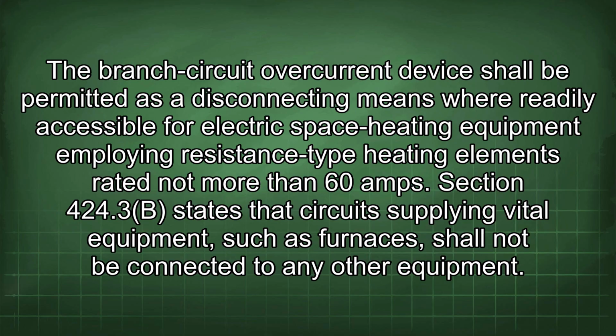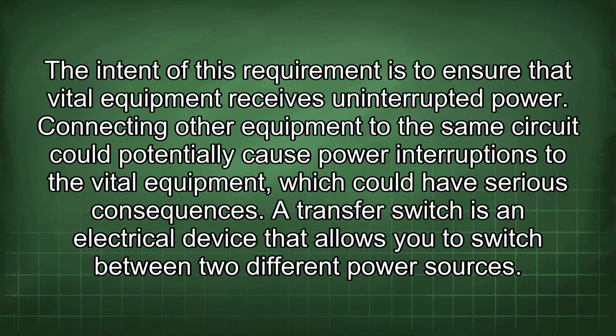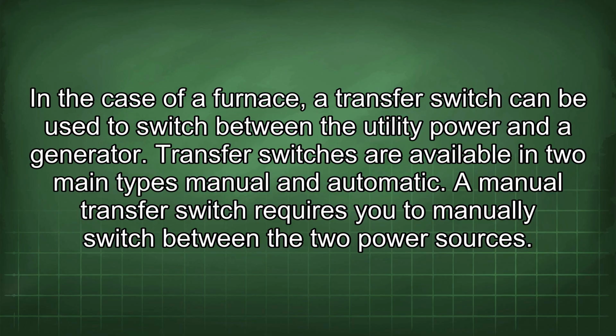Section 424.3(B) states that circuits supplying vital equipment, such as furnaces, shall not be connected to any other equipment. The intent of this requirement is to ensure that vital equipment receives uninterrupted power. Connecting other equipment to the same circuit could potentially cause power interruptions to the vital equipment, which could have serious consequences. A transfer switch is an electrical device that allows you to switch between two different power sources. In the case of a furnace, a transfer switch can be used to switch between the utility power and a generator.